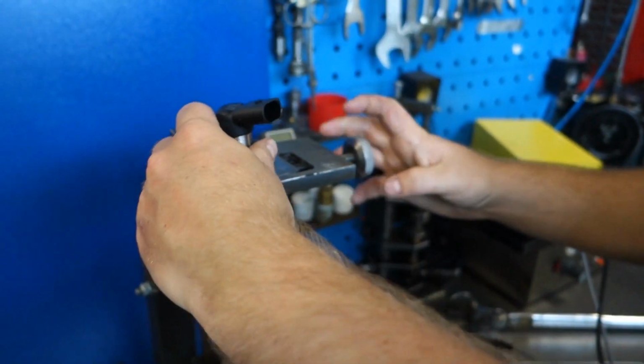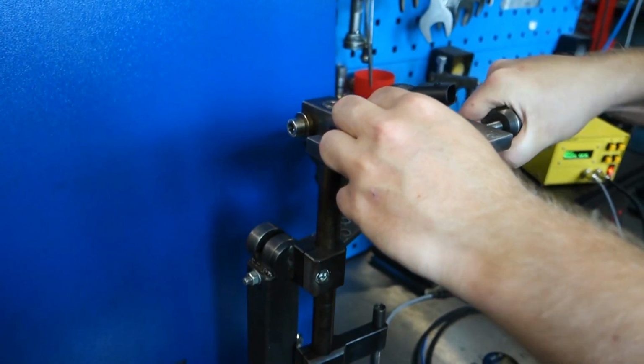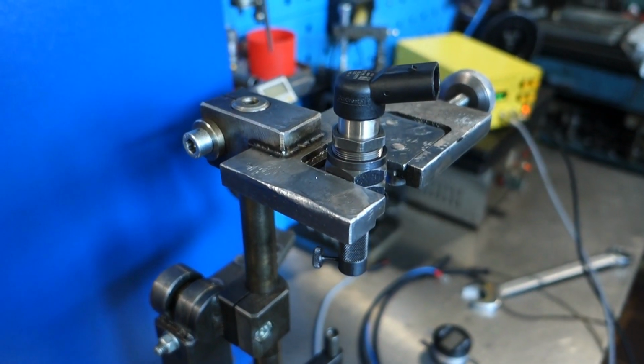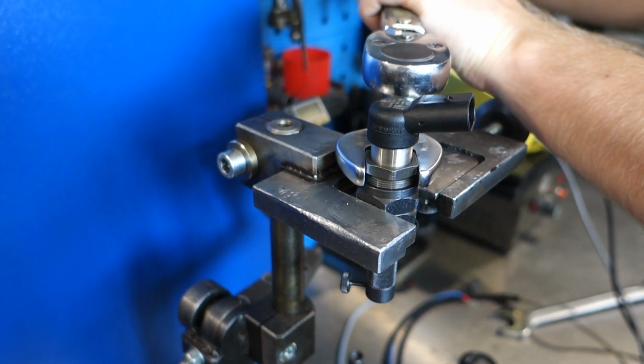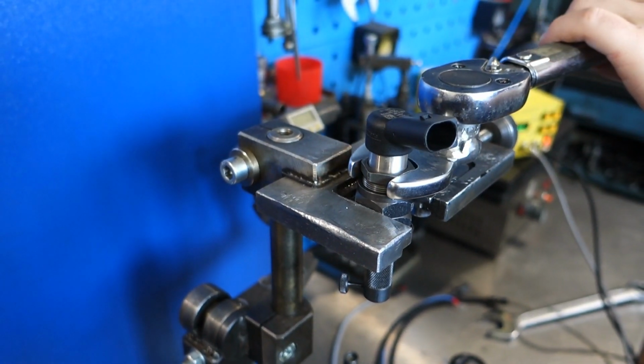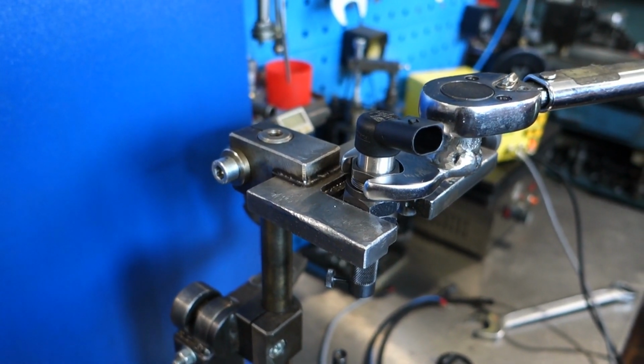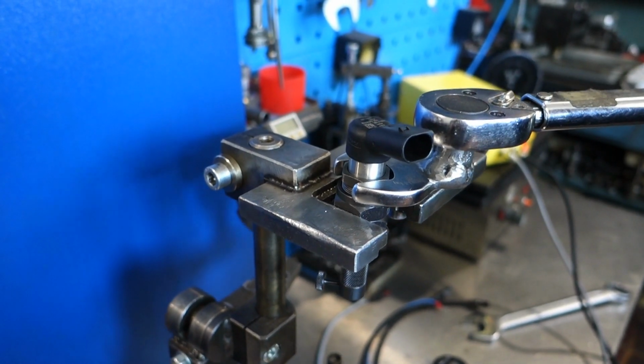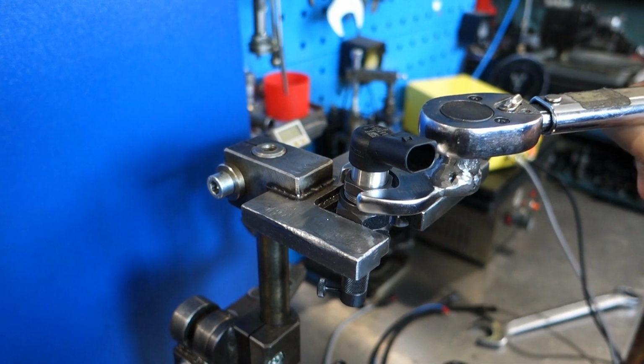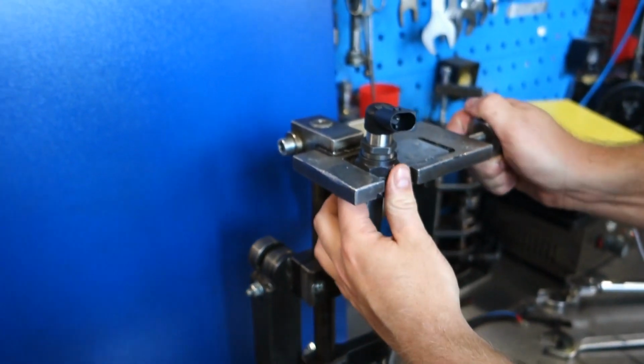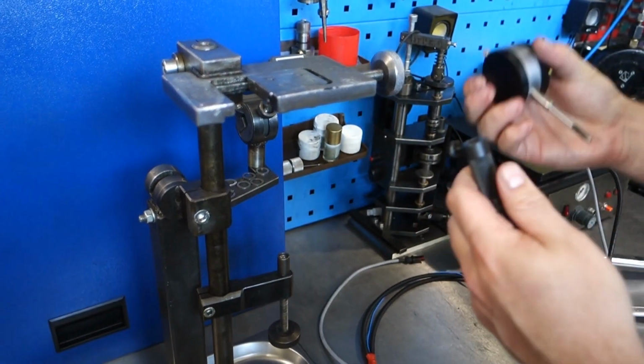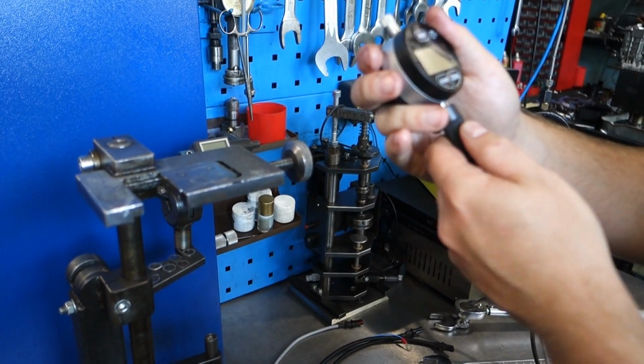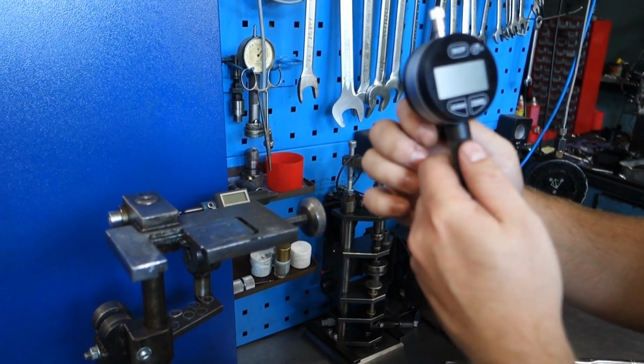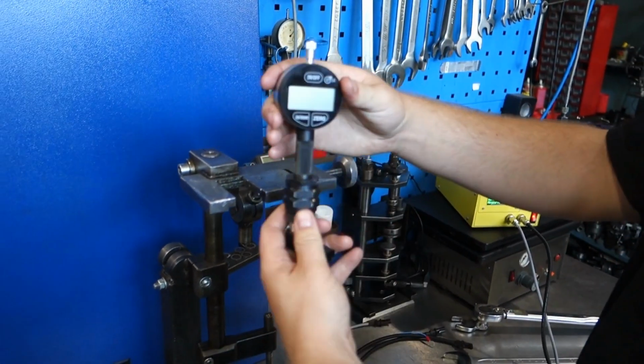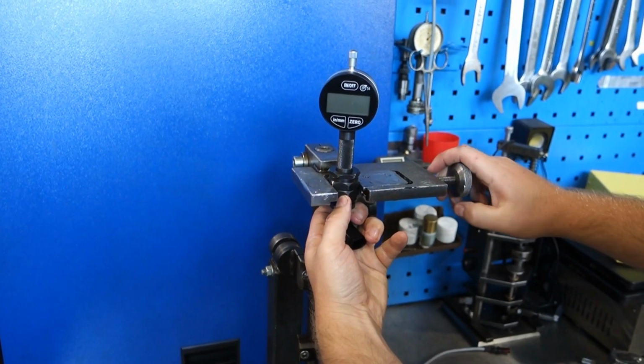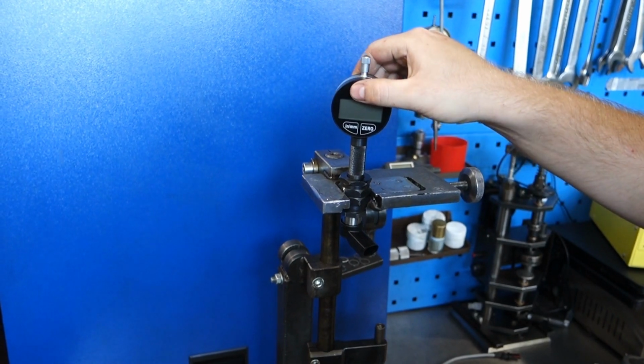Alright, what we need to do is tighten it with a torque wrench at 40 newtons or 4 kilograms to make sure that calibration later on in the process will be perfect. So we're tightening it onto the adapter with 40 newtons on the torque wrench. Make sure your staple doesn't move, this is possible. There we go. Now that that's done, we can place the micrometer back into its adapter. Tighten it up. Place it back. Make sure it's zeroed.